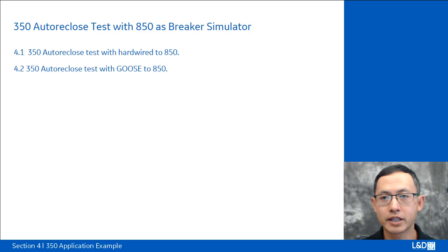In the application example of 350, we're going to test 350 auto-reclose by using 850 as a breaker simulator. First, we're going to use a hardwired connection between the 350 and the 850. We're also going to set up the transient recorder to capture the waveform of the 4 shots auto-reclose.